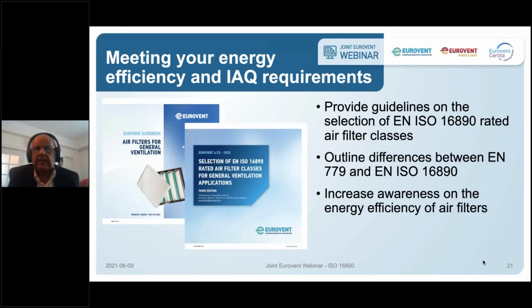So basically, what is happening is that at Eurovent certification, they have been able to grade the filters depending on the kilowatt hour that a filter consumes working for one complete year. You will see that the gradation goes from a value of say 700 or 800 kilowatt hours for the best possible filter that manufacturers have designed, to almost double that value for a lower grade energy class filter.